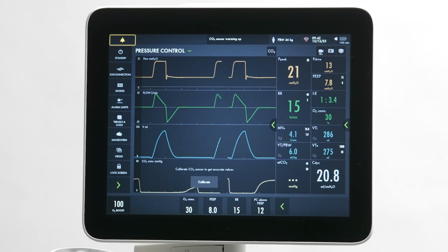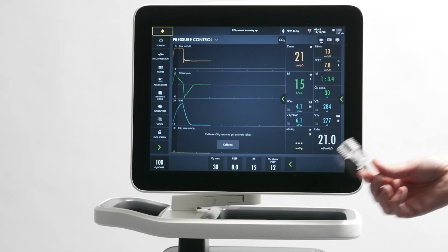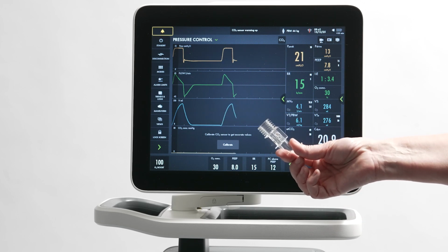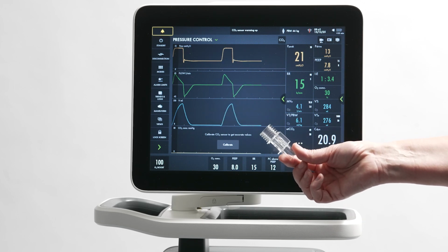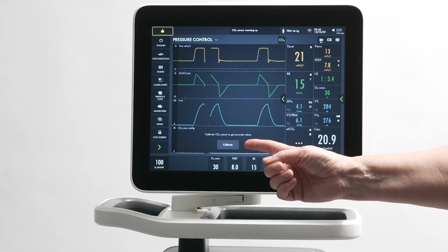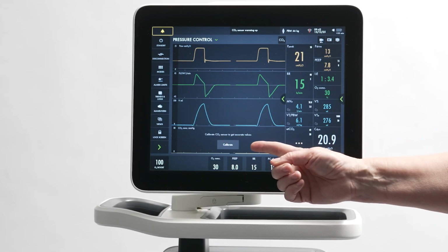The CO₂ sensor must be calibrated using an airway adapter. There are two adapters available. The white adapter is for the adult patients and the red adapter is for the infant neonatal patients. If calibration is necessary, a message will appear on the screen.